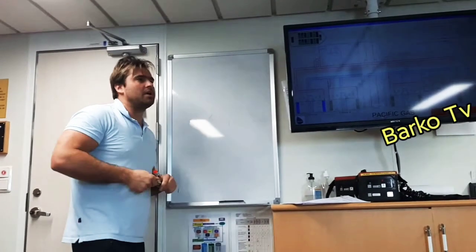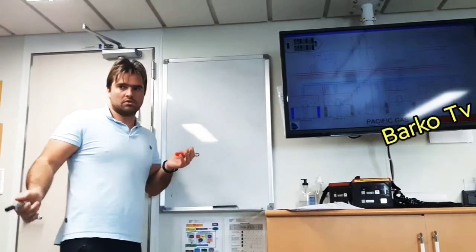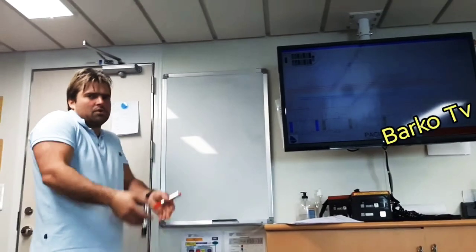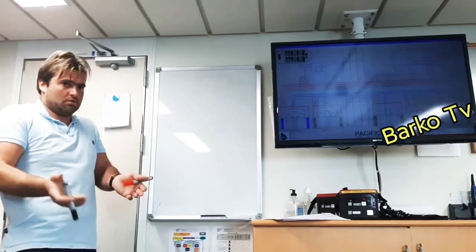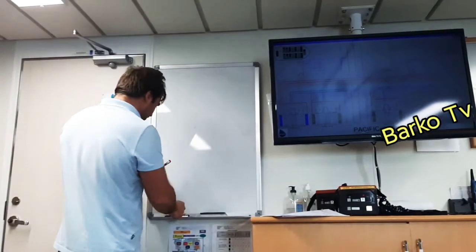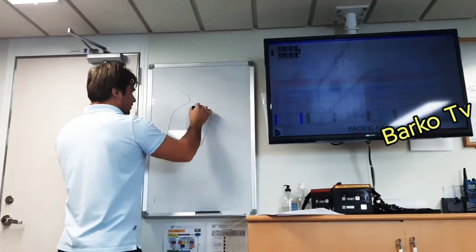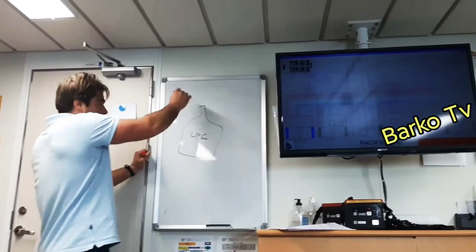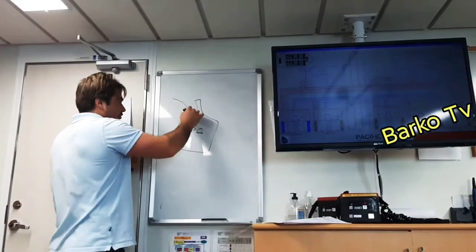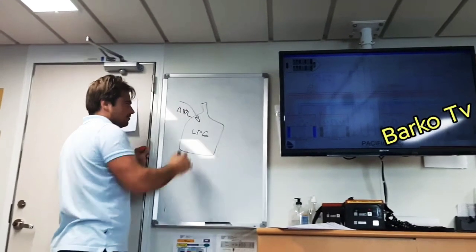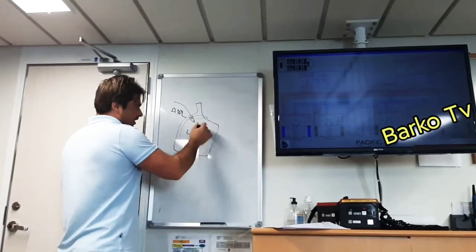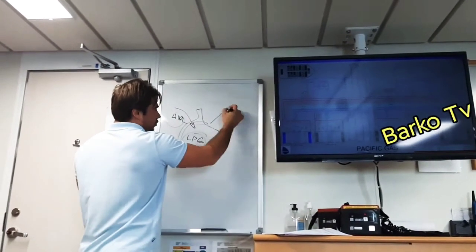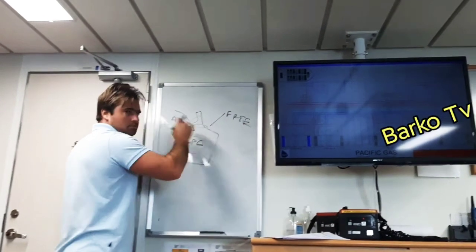Why are we changing the atmosphere? What is the purpose? Why do we always say we have the LPG tank, and then we put the nitrogen there, then we put the air there? Nobody knows, but the purpose is that if you want to go in the tank and you put air directly, the mixture of air and LPG inside can reach a concentration where, if you put fire, it will explode.